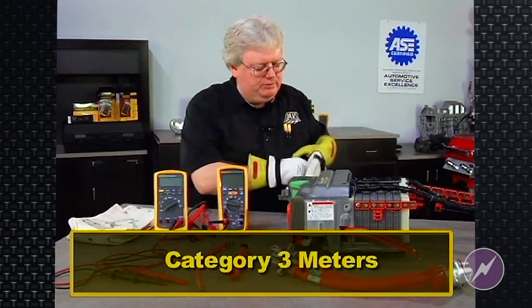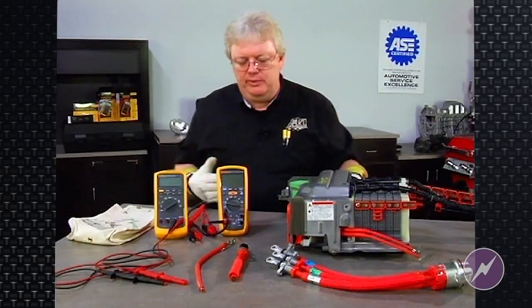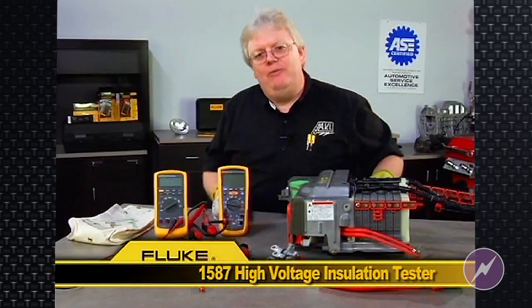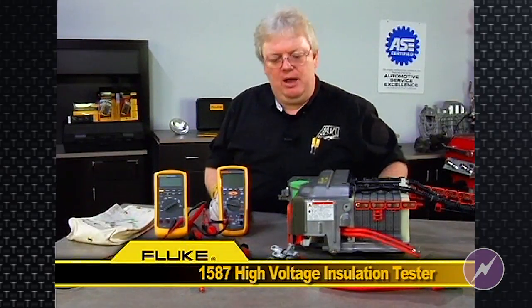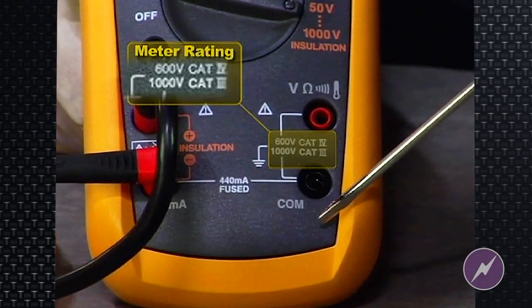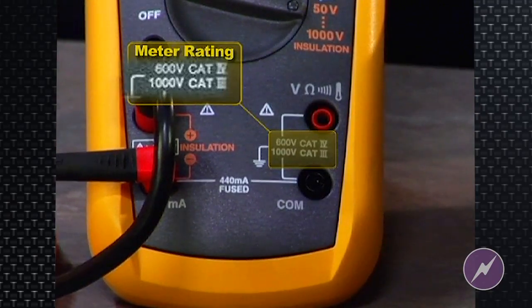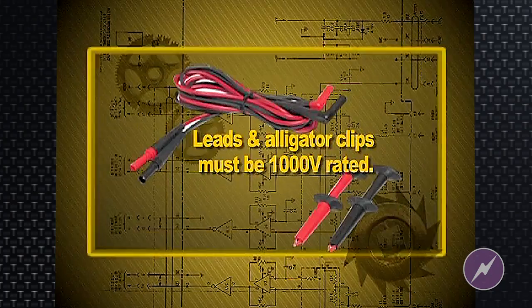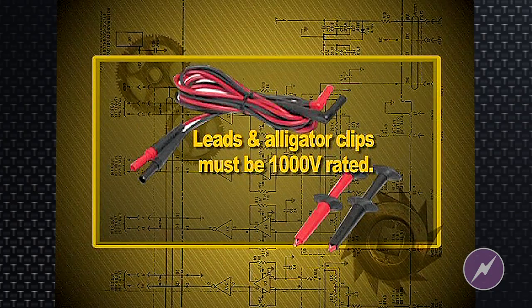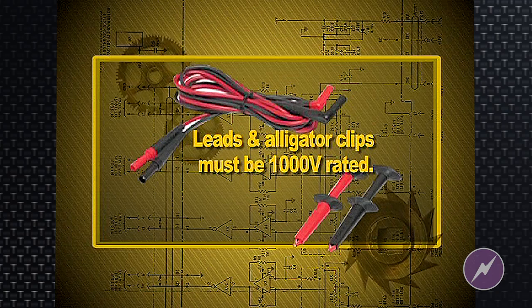Most of the Fluke products are Category 3 now — the 5 series, 87s, 88s, they're all Category 3. And of course this Fluke 1587 high voltage insulation tester is also a CAT 3, 1000 volt meter. You can find the rating of that meter in the lower right-hand corner of all the products. No matter what brand of meter it is, it will say whether it's CAT 3, 1000 volts or not. This is actually CAT 3, 1000 volts and CAT 4, 600 volts. So make sure not only the meter is specified to that degree of protection, but also make sure the leads say 1,000 volts, as well as the ends — the alligator clips or probes.